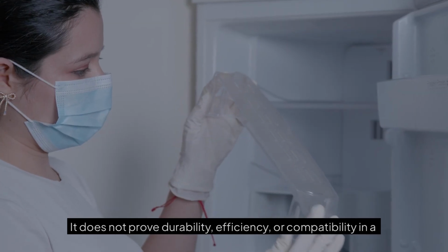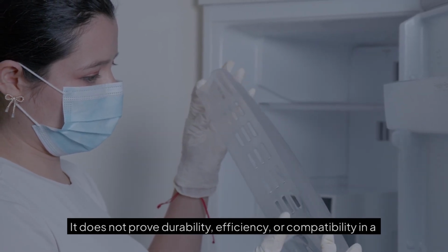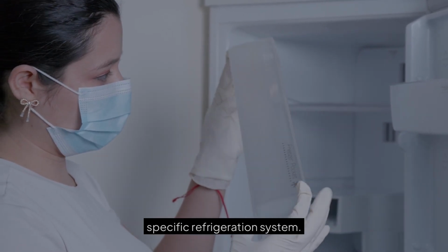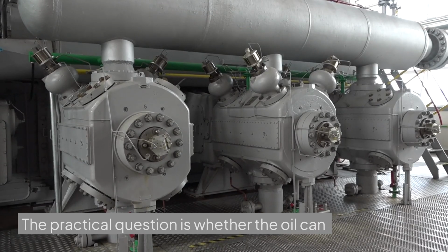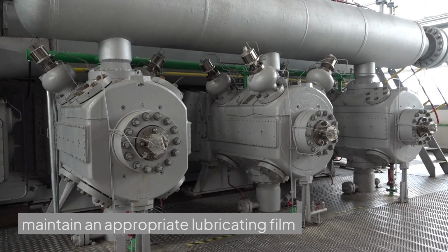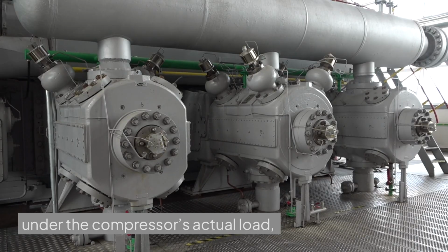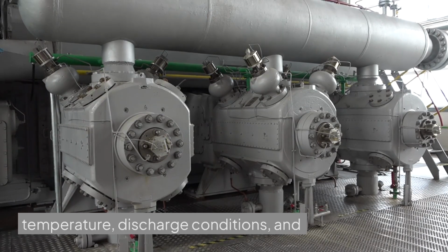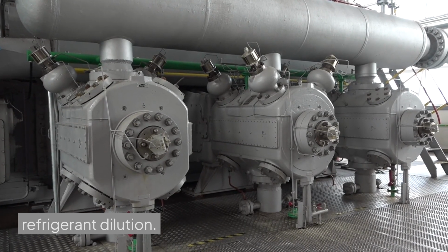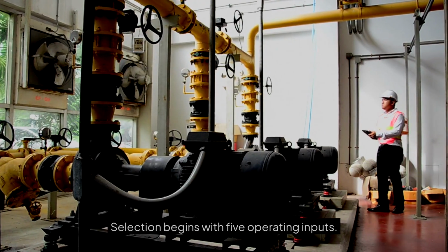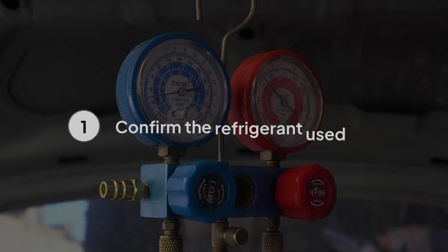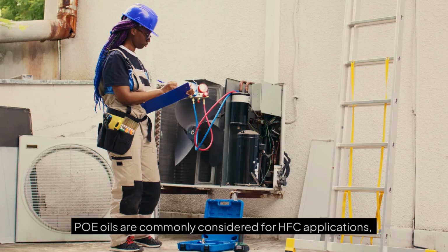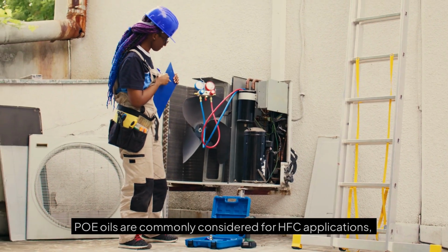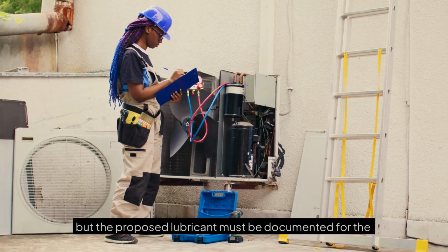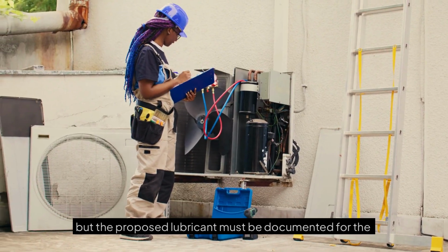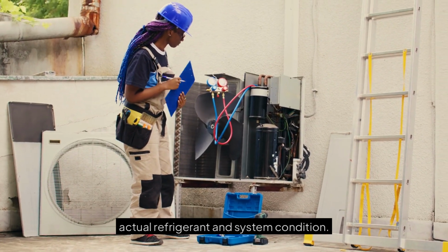It does not prove durability, efficiency, or compatibility in a specific refrigeration system. The practical question is whether the oil can maintain an appropriate lubricating film under the compressor's actual load, temperature, discharge conditions, and refrigerant dilution. Selection begins with 5 operating inputs. First, confirm the refrigerant. POE oils are commonly considered for HFC applications, but the proposed lubricant must be documented for the actual refrigerant and system condition.